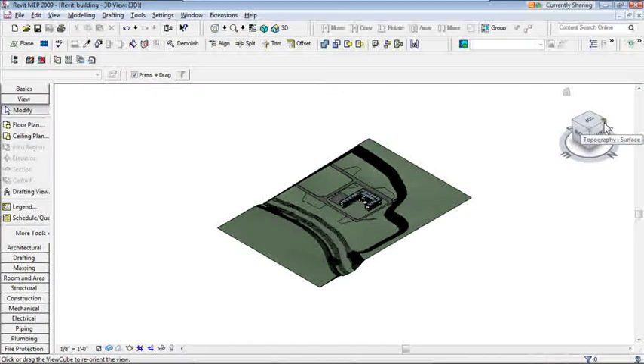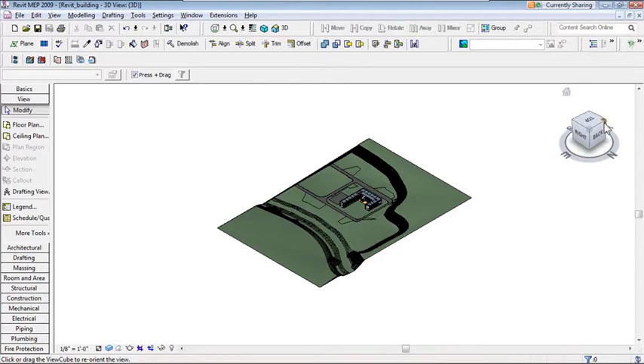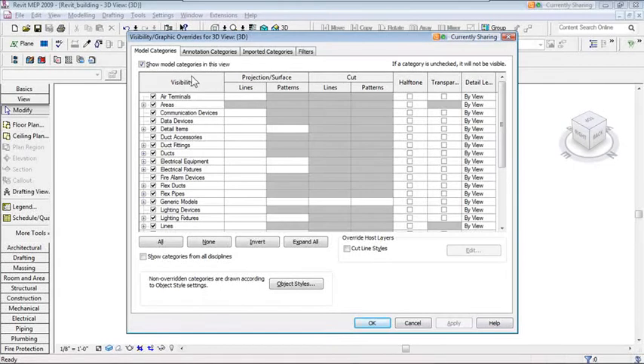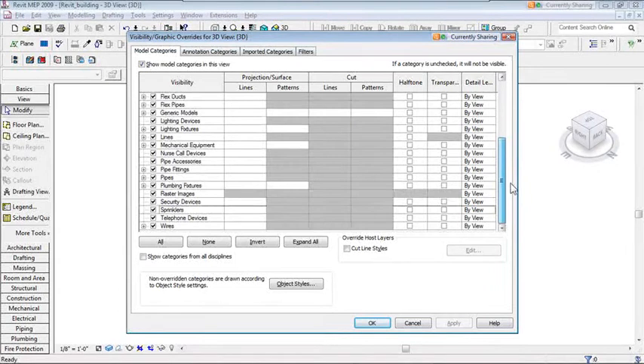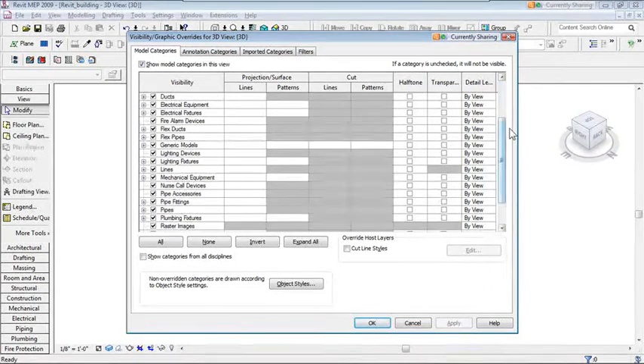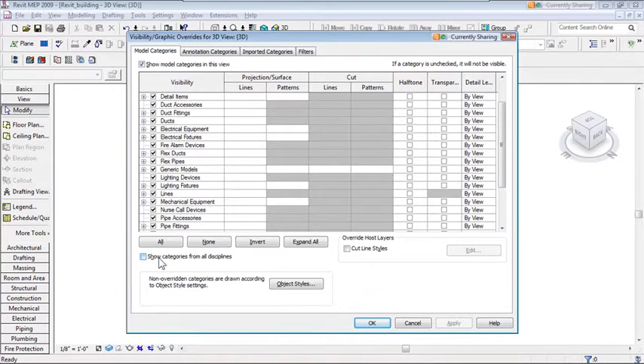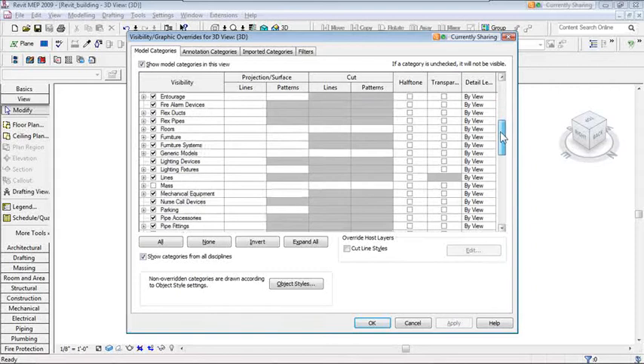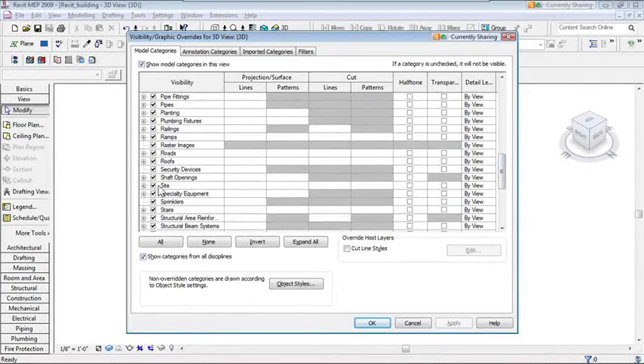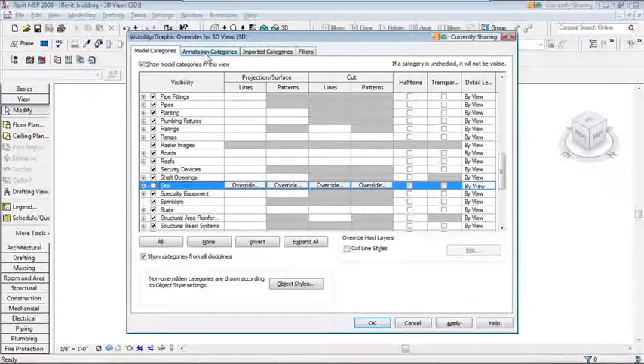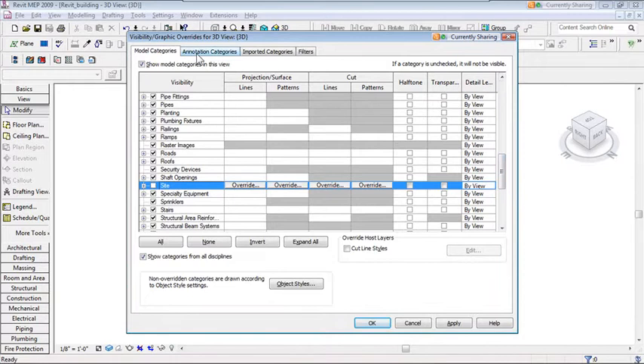The zoom extents is too large because it includes the site plan. To fix this, type VV — the shortcut for Visibility Graphics. This controls what categories are turned on in the current view. The default list shows MEP content like plumbing, electrical, and ductwork. Click 'Show All Categories and All Disciplines' to also see architectural elements. Then uncheck Site to hide the site plan.